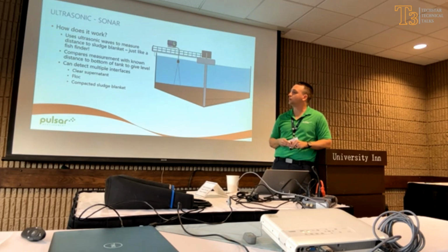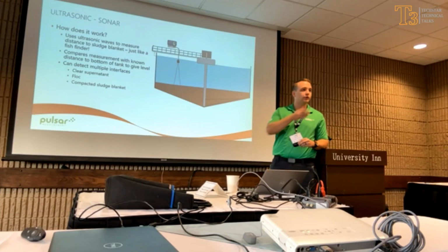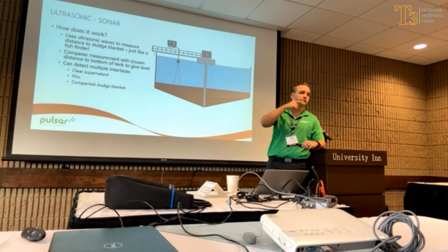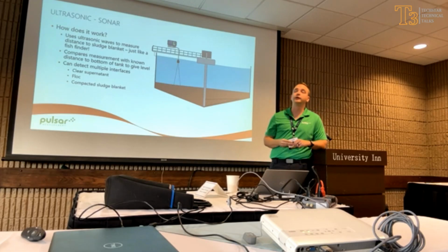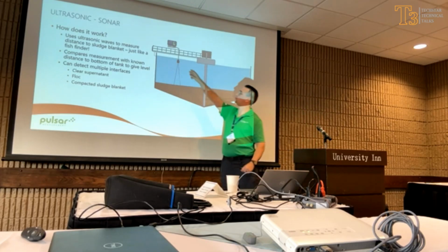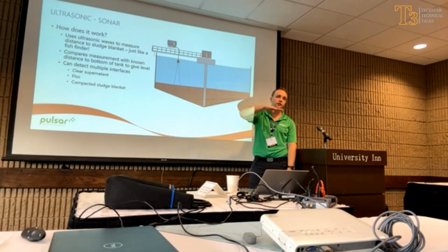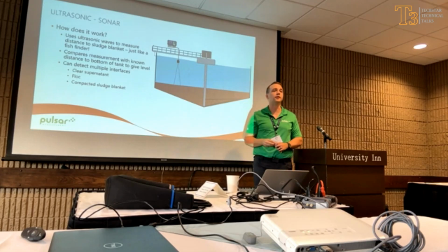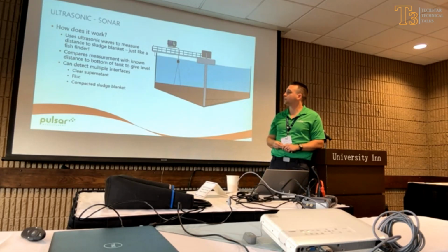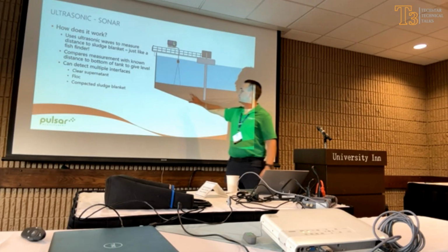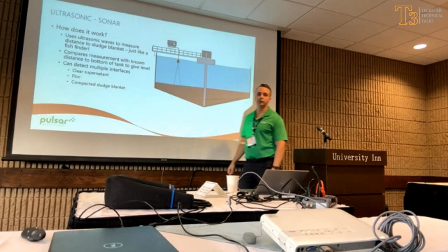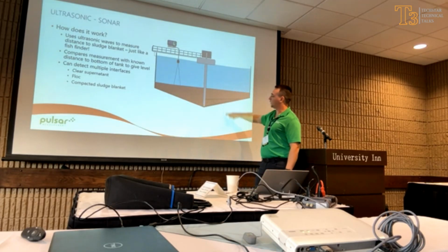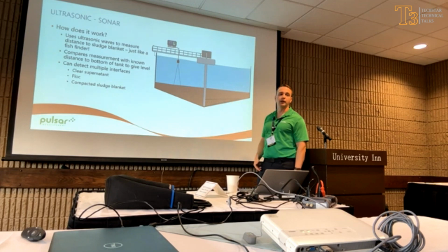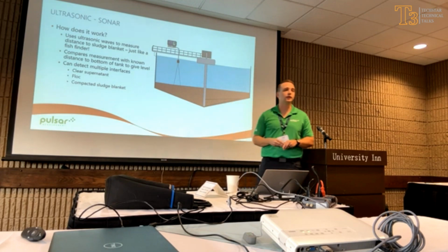So it's something you want to make sure is reading correctly. And to your point, when the skimmer comes around and kicks up that bottom, you want two things. First, if the sensor's inserted into the water, you want something that will kick that sensor up, move it out of the way, and drop it back down without losing the measurement. Something that dampens that measurement and isn't overly reactive. Otherwise your data is going to jump every time the skimmer comes around, and you'll get variance from the blanket not being settled.